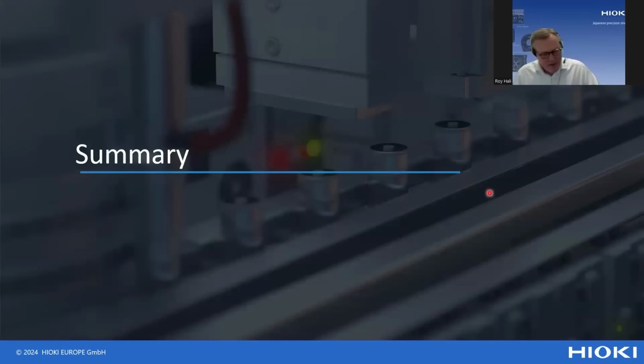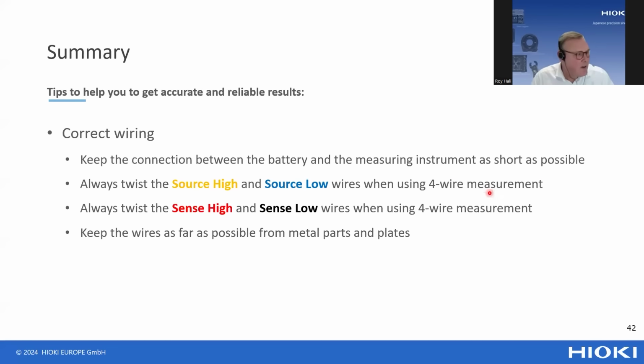So this closes basically all the technical information that we wanted to share. And we're going to look in a short summary at what has been told. First, of course, wiring. Main message is keep your wiring between the battery tester and the battery as short as possible. Always twist the source high and source low wires and the sense high and sense low wires. And keep your wiring far away from metal parts and plates. Those are the ground rules that you have to follow.